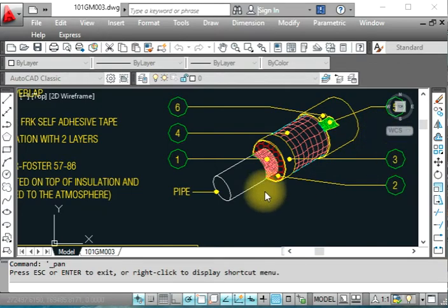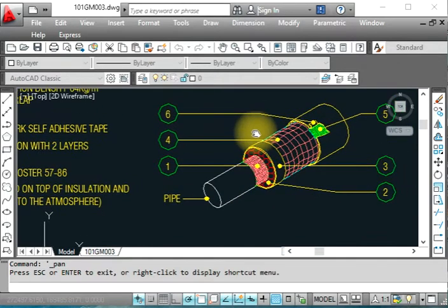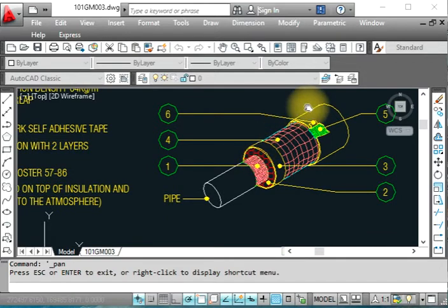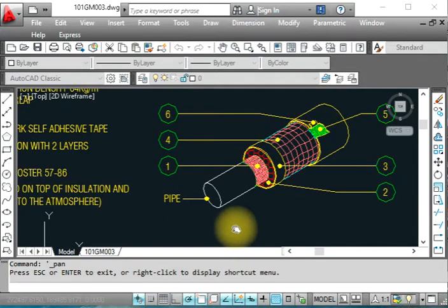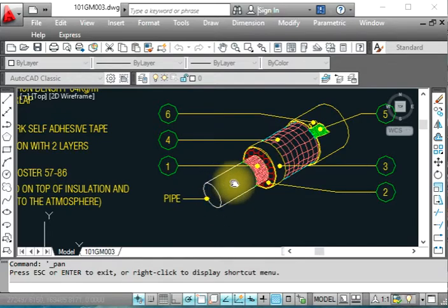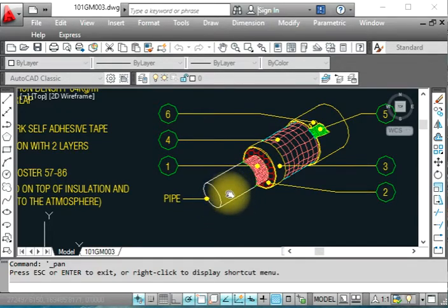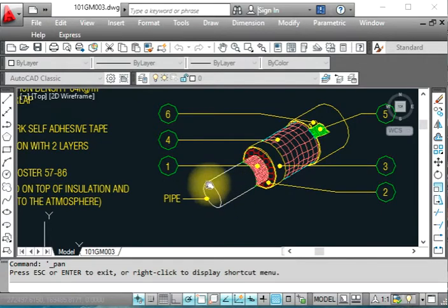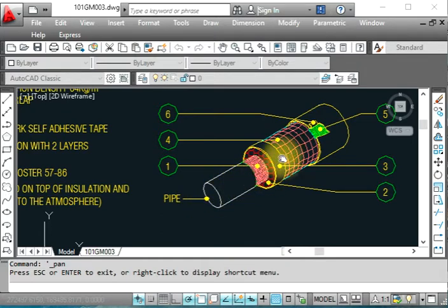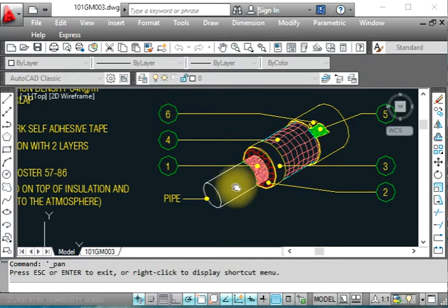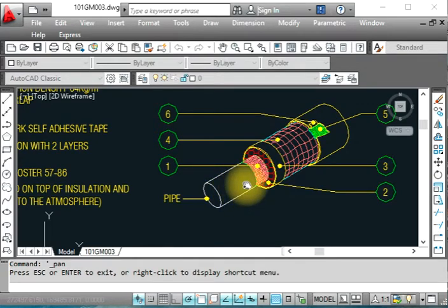Finally, I bring the video for chilled water insulation. Chilled water pipes need insulation because we are using black steel pipe, usually seamless schedule 40 or schedule 80, as per the specification and client requirements. We must insulate the pipe because of condensation. I will show you how they insulate the pipe in the original installation.